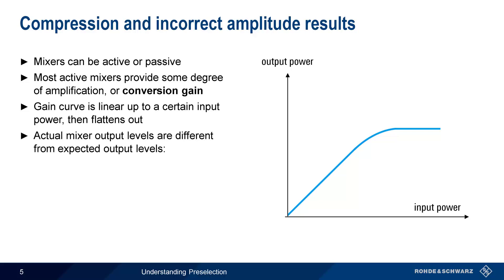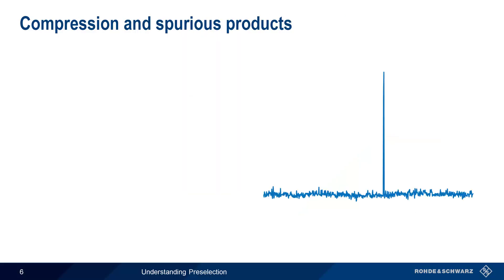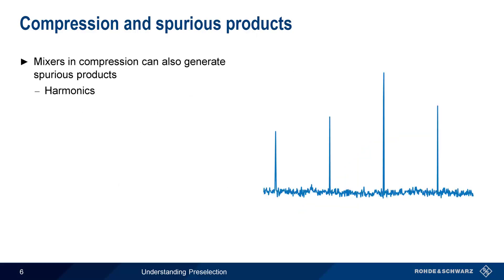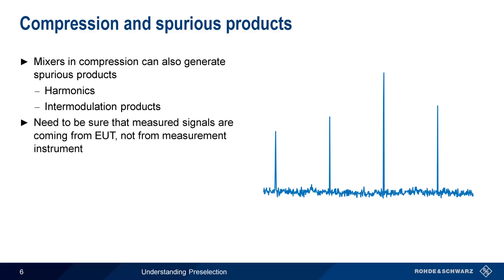The result is that the actual mixer output levels are different than the expected mixer output levels. In most cases this incorrect amplitude is lower than the expected levels, but can actually be higher in some cases, depending on the idiosyncrasies of a particular mixer's design. A mixer in compression can also generate distortion in the form of spurious products, such as harmonics and intermodulation products. In many applications, and especially in EMI measurements, these spurious signals are a significant issue. We want to be sure that the signals we are measuring are actually coming from the equipment under test, not from the measurement instrument itself.